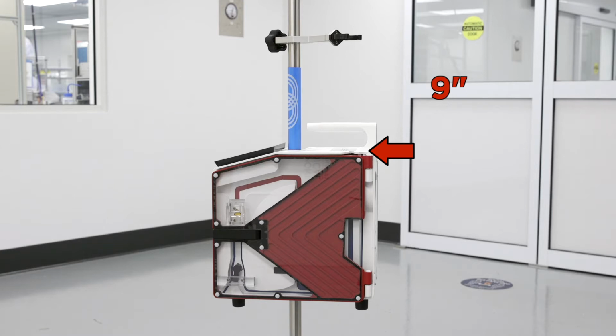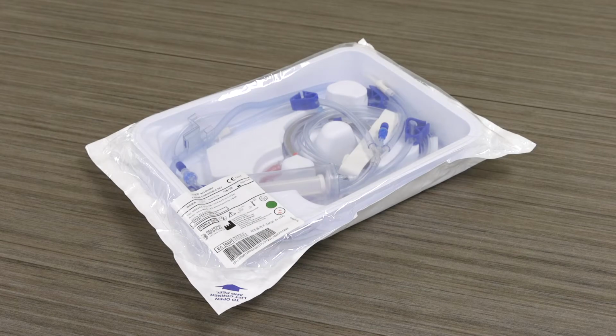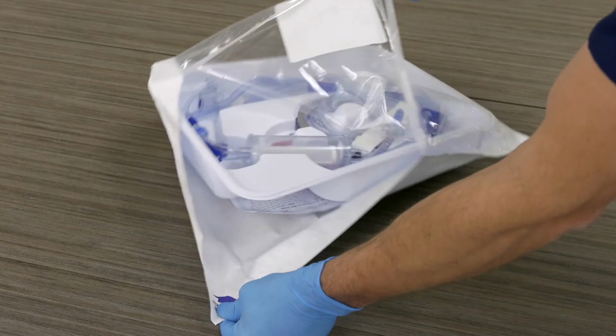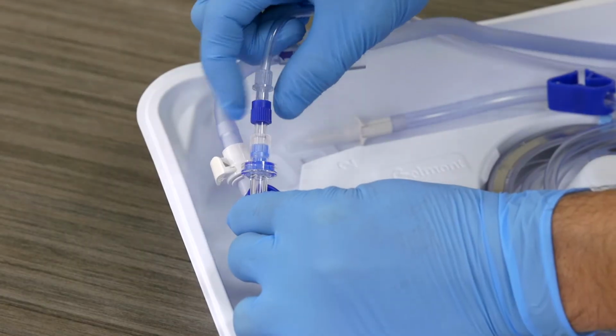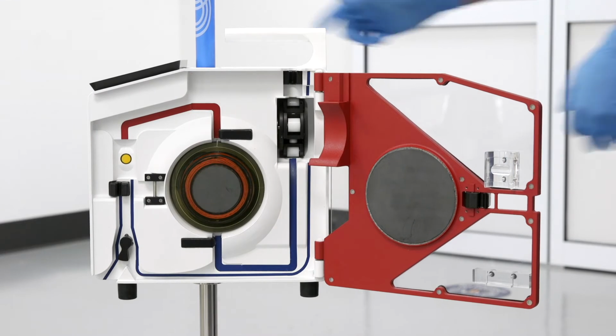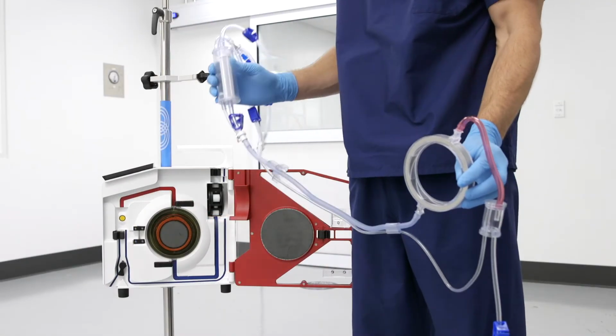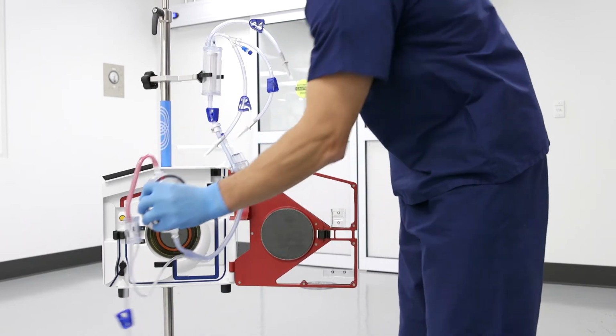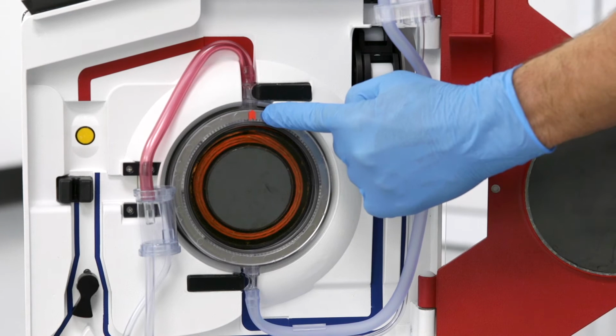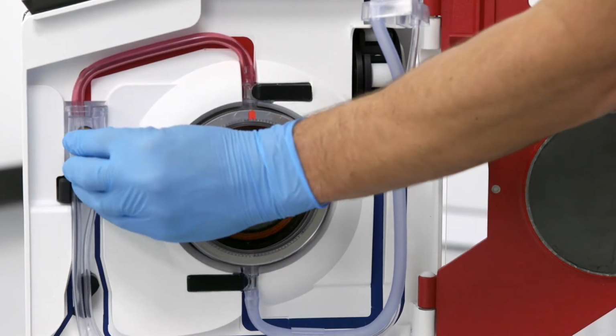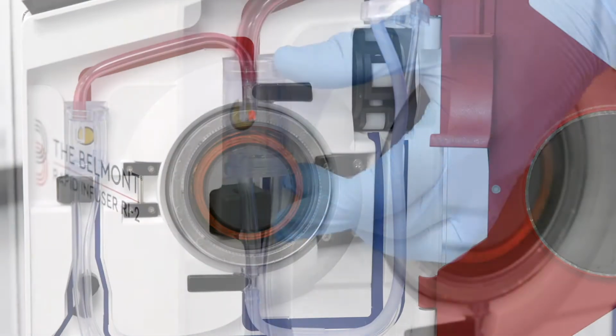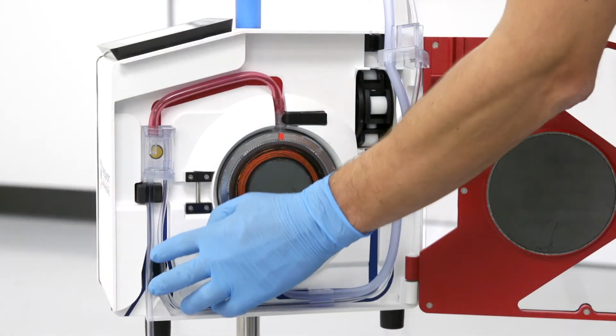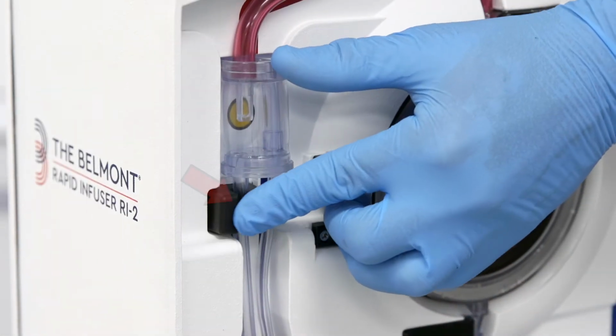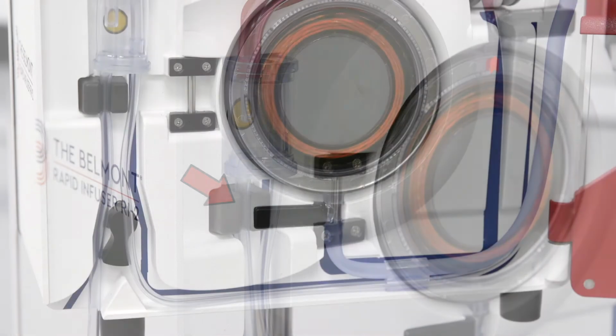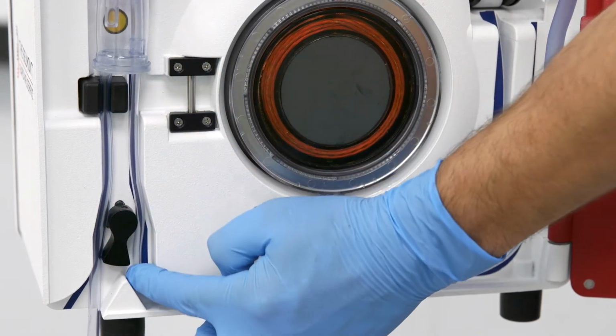Install the small reservoir support approximately 9 inches above the top of the system. The single patient use disposable comes pre-assembled in a sterile container and is color-coded for easy installation. Begin by opening the disposable package and tightening the two luer locks. Open the door of the unit. Holding the heat exchanger in your left hand and reservoir chamber in your right, snap the reservoir chamber into the holder. Insert the heat exchanger with the red arrow pointing up. Align the red tubing on top of the red stripe and place the pressure chamber into the pressure channel. Press the infuse line into the secondary air detector to the left of the patient safety valve wand. Note, the infuse line should be at or below flush within the air detector. Place the thinner recirculation line to the right of the air detector and to the right of the valve wand.